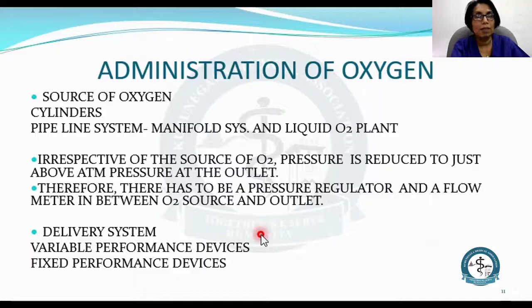This is an oxygen cylinder. At a glance, you can say that it's an oxygen cylinder because it's color-coded. Black body and a white shoulder. This is an oxygen regulator. It reduces oxygen pressure in the oxygen cylinder and then it delivers to the oxygen flow meter. This is the flow meter.